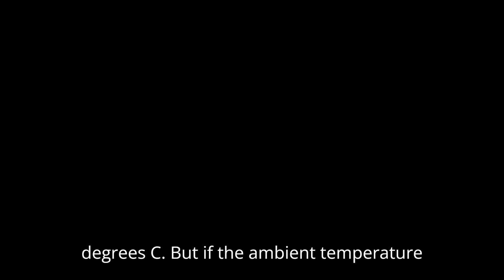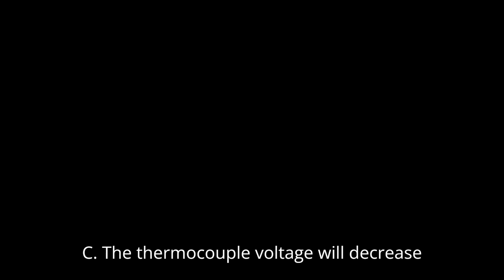Yeah. If the transmitter doesn't know the actual temperature of that cold junction reference point, the overall reading will be wrong. For example, if the hot junction is at 500 degrees C and the cold junction is at 25 degrees C, the thermocouple generates a voltage corresponding to a difference of 475 degrees C. But if the ambient temperature rises and the cold junction heats up to 35 degrees, the actual temperature difference is now only 465 degrees C. The thermocouple voltage will decrease accordingly. If the transmitter isn't aware that the cold junction temperature changed, it will incorrectly report a lower process temperature, even though the process itself hasn't changed at all. I see. The measurement drifts with the ambient temperature at the connection point.